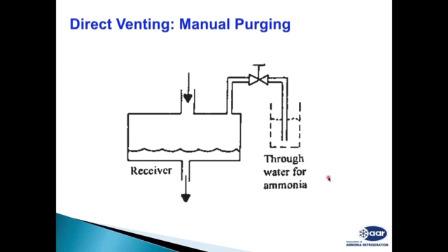Typically, with manual purging, we have a purge valve provided at the receiver or at the inlet of the condenser. It means we have to do it manually: shut down the plant and let the water run in the condenser for maybe an hour or so. Whatever ammonia gases are there are cooled down and become liquid, and what is left at the top is air. You must understand the density of air is lower than ammonia, so air will go up and ammonia liquid will go down.